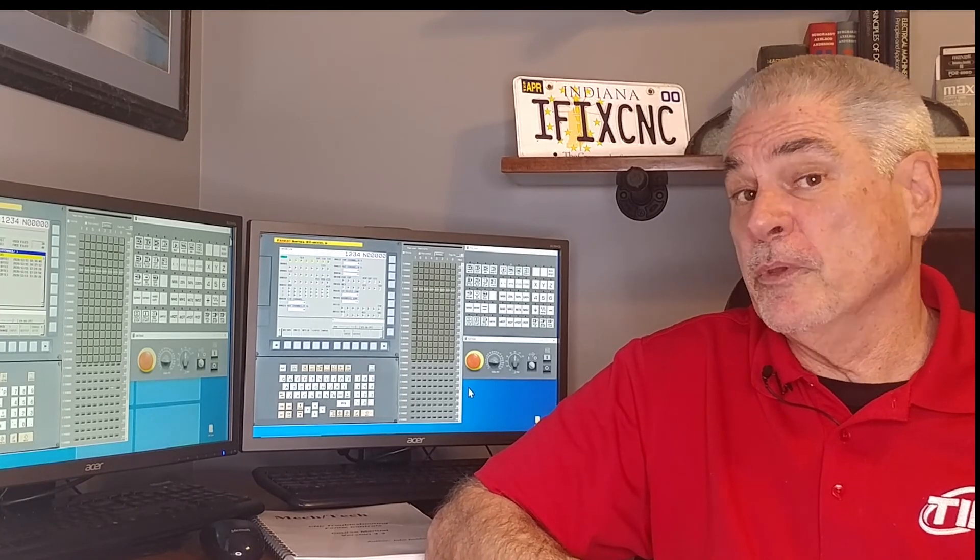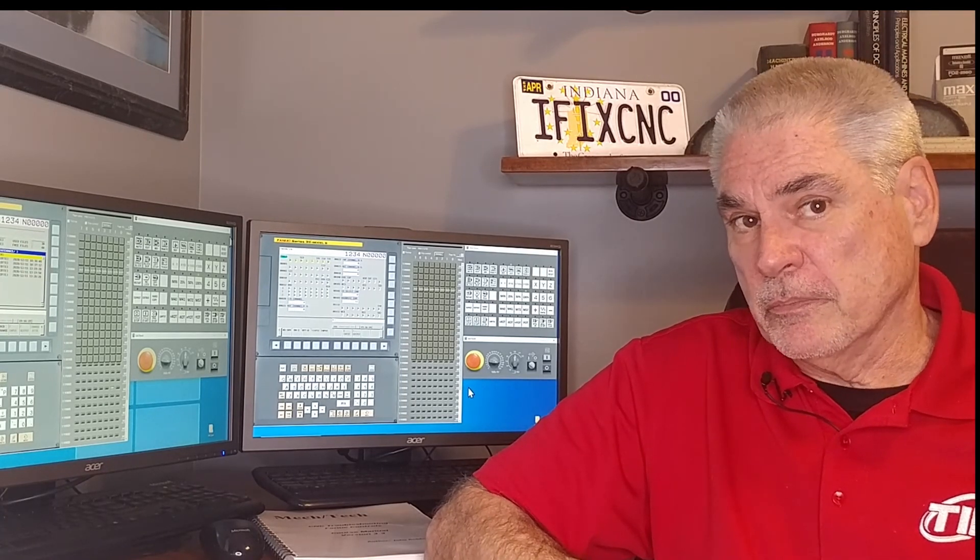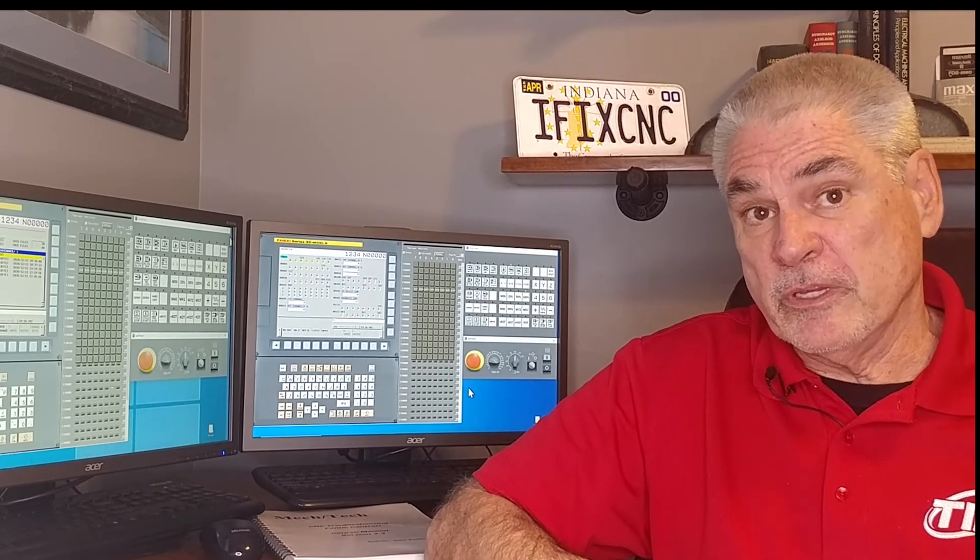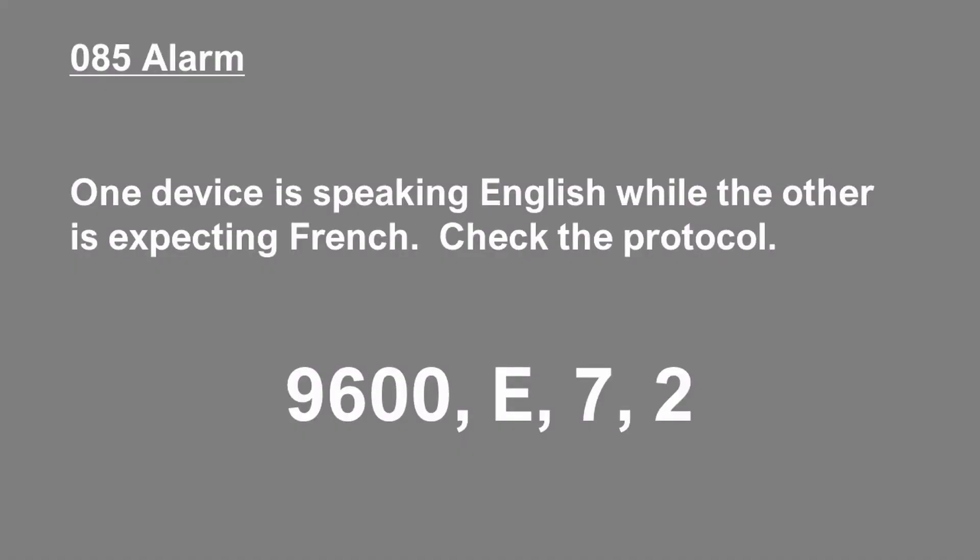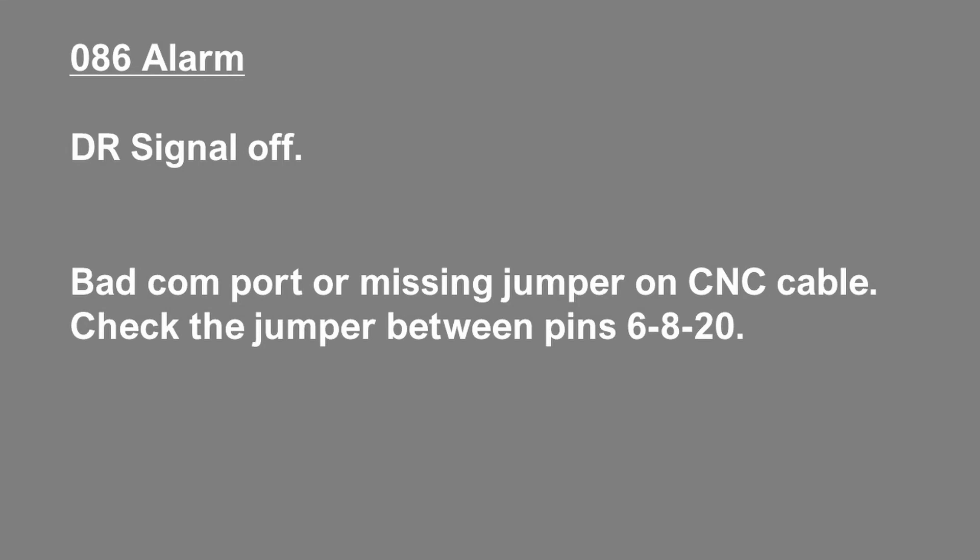There are some alarms that are associated with the RS-232 communication system. Let's take a look at some of these. The 085 alarm is a communications error. Check the protocol settings. Somebody is not agreeing on how they're going to talk. The 086 alarm. DR signal off. This one is normally caused by a problem with the cable. Verify the jumper wires.